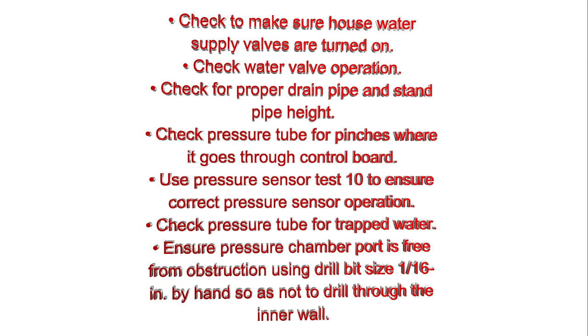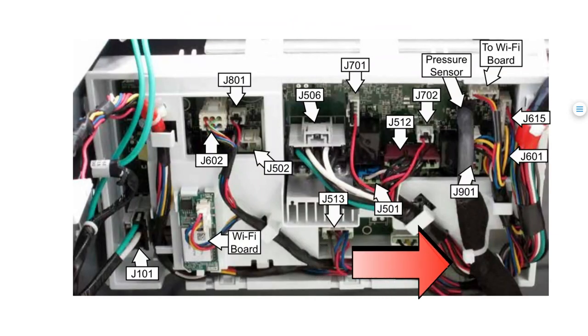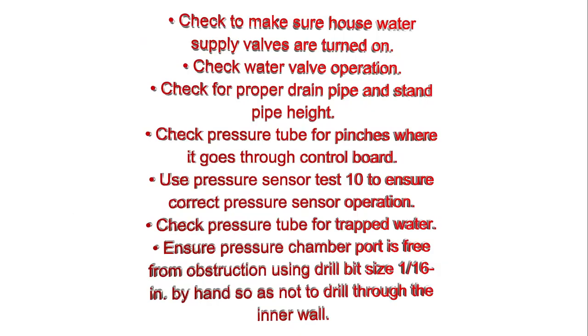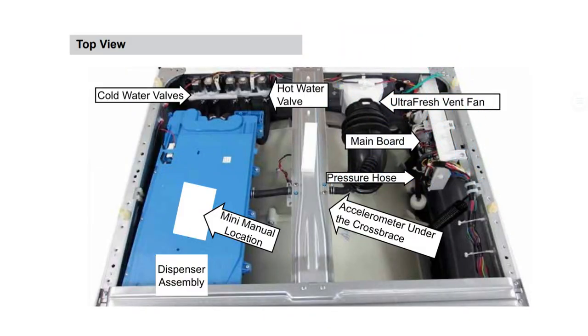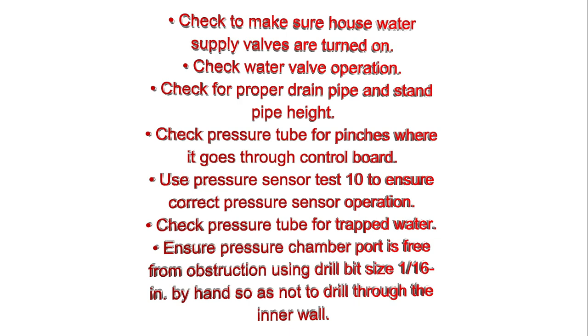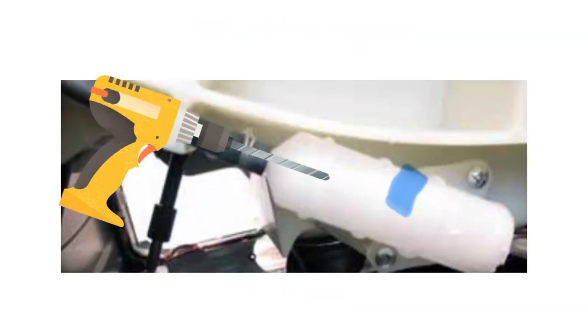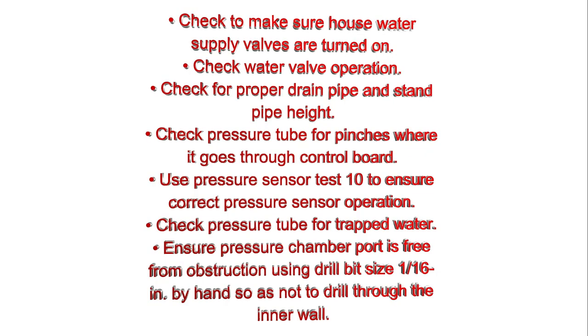Check pressure tube for pinches where it goes through control board. Use pressure sensor test 10 to ensure correct pressure sensor operation. Check pressure tube for trapped water. Ensure pressure chamber port is free from obstruction using drill bit size 1/16 in by hand so as not to drill through the inner wall.